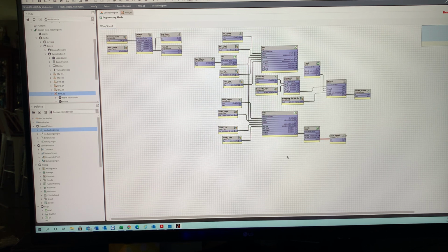At 60%. Then this air handler, this particular one for this church, had a preheat and a reheat. So what it would do is it would preheat the return air to get it above the dew point. So that way, as we're trying to draw the moisture out through the chill water coil, it would make it a good return temp, usually around, I think they were trying to maintain around 74 to 70 degrees on the return. And then we would reheat the discharge air temp to maintain the space temp. It was a fun program, and there was a lot of logic.